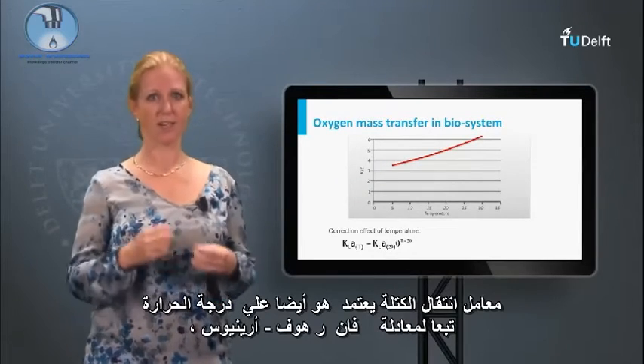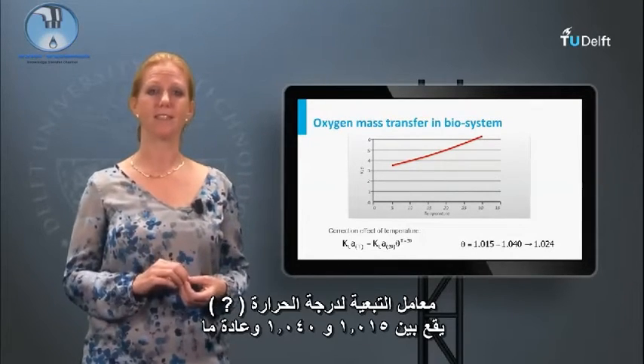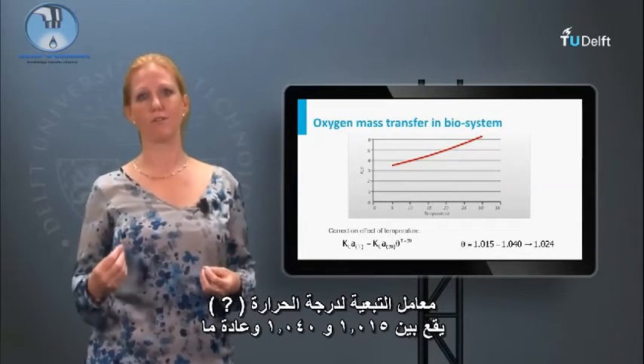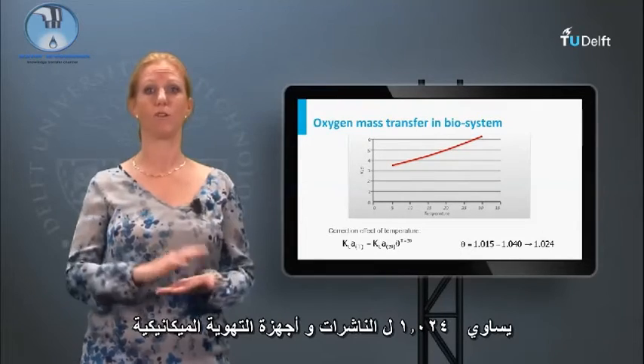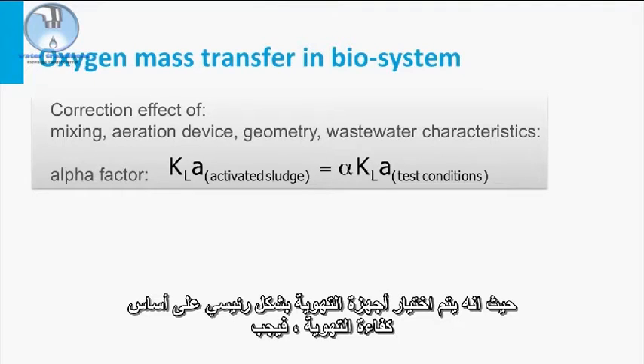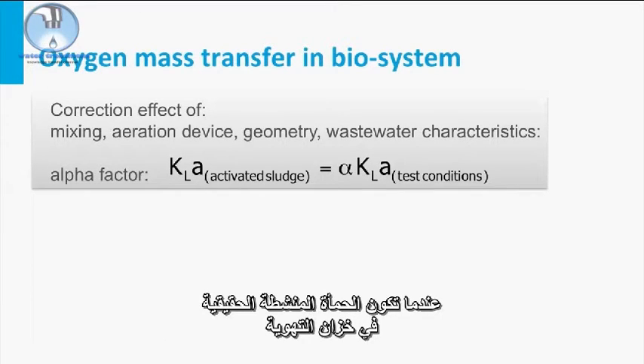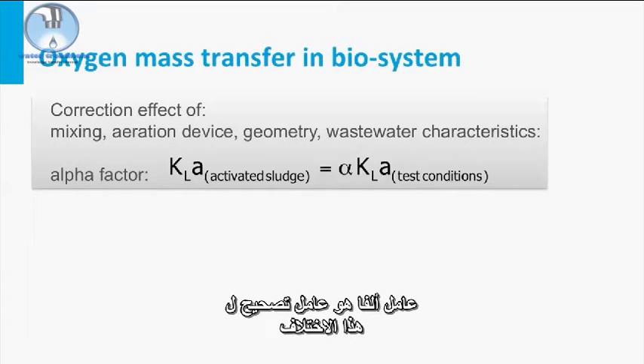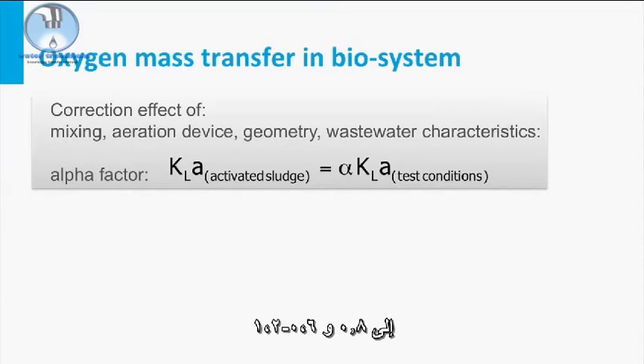The mass transfer coefficient is also temperature dependent, following the van 't Hoff-Arrhenius equation. The temperature dependency coefficient lies between 1.015 and 1.040 and is typically 1.024 for diffusers and mechanical aerators. Since aerators are mainly chosen based on aeration efficiency, the alpha and beta factors have to be considered too. Since the mass transfer coefficient is often measured in clean tap water, it can change when real activated sludge is in the aeration tank. The alpha factor is a correction factor for this difference. Alpha factors for diffused aerators and mechanical mixers are respectively in the range of 0.4 to 0.8 and 0.6 to 1.2.